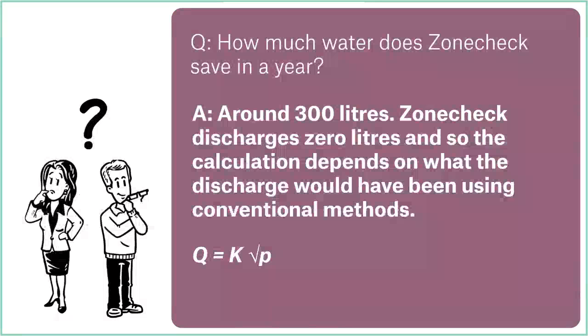And then it also depends on the pressure. Obviously the higher the pressure, the more water is going to be discharged. And that is found in this equation: Q, which is the flow rate, equals the K factor times the square root of the pressure. So to get a nice, easy calculation, let's say we're going to use K160 as our K factor. The pressure will go for 4 bar, because the square root of 4 is 2, so that's nice and easy. So it's 160 times 2, which is 320 litres per test.